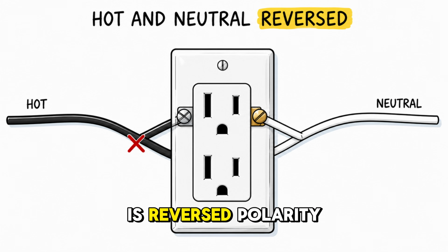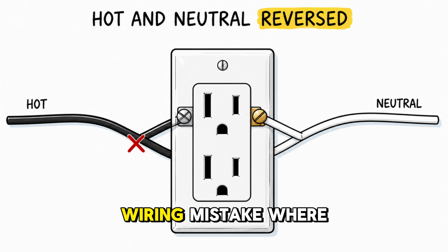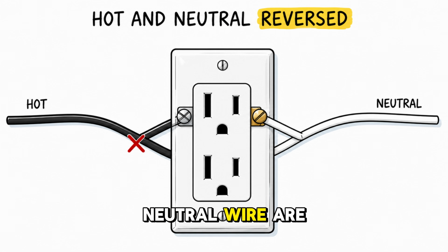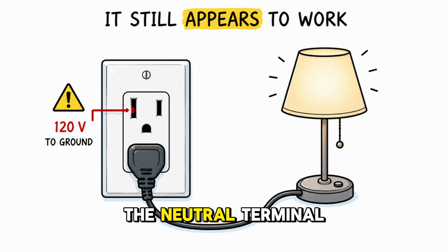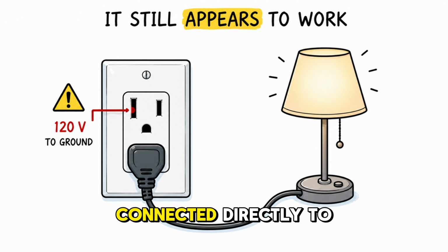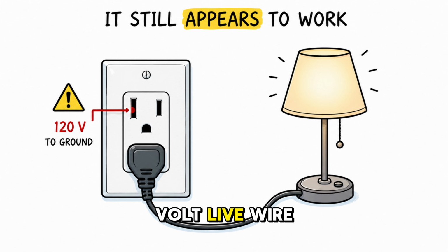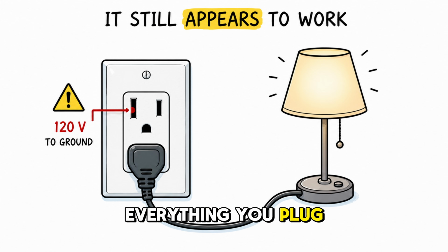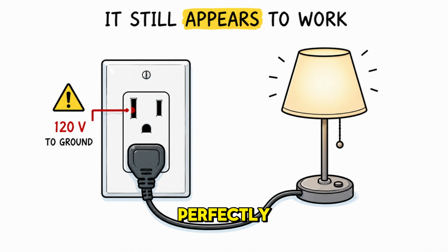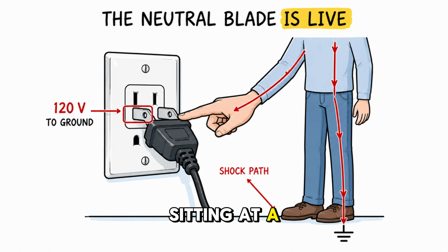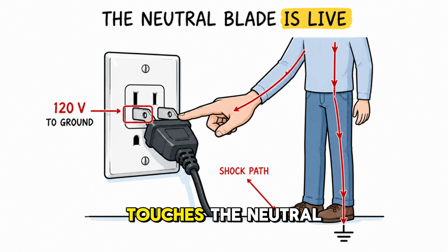The third condition is reversed polarity. This is a wiring mistake where the live wire and the neutral wire are connected backward at an outlet. It is far more common than anyone admits. In this scenario, the neutral terminal on that outlet is actually connected directly to the 120-volt live wire inside the wall. The outlet still functions. Everything you plug into it appears to work perfectly. But the neutral slot is now sitting at a full 120 volts. Anyone inserting a plug who accidentally touches the neutral prong receives a full voltage shock.